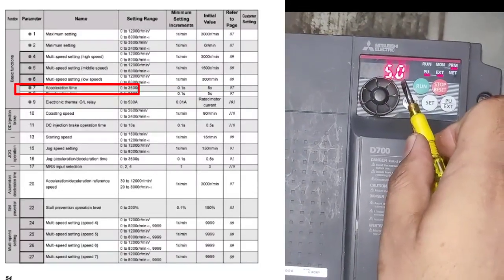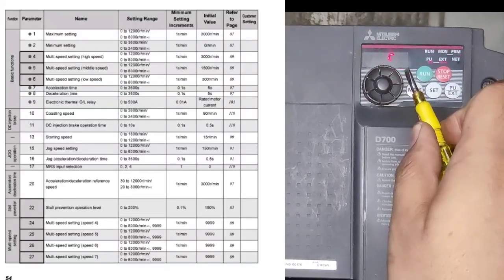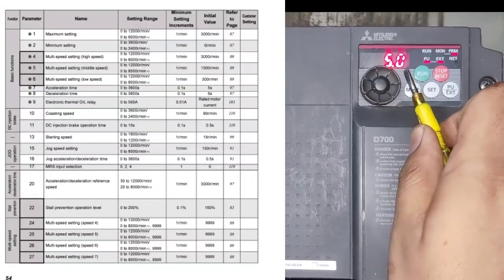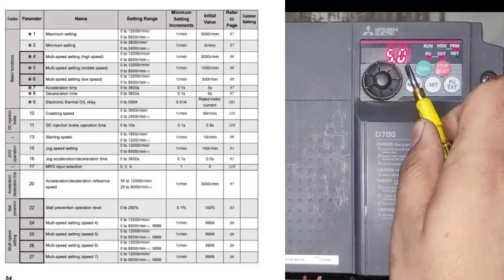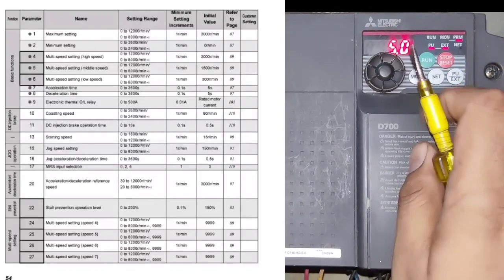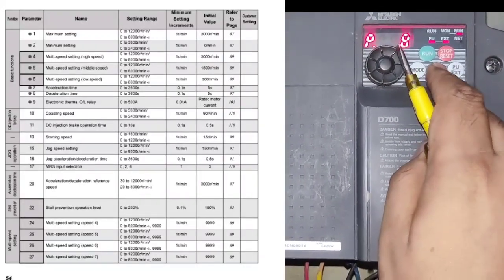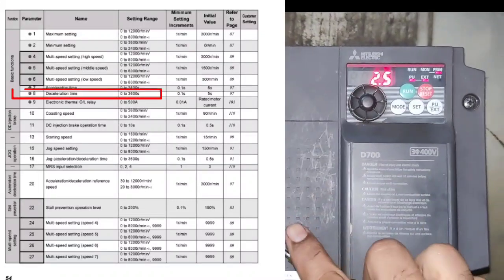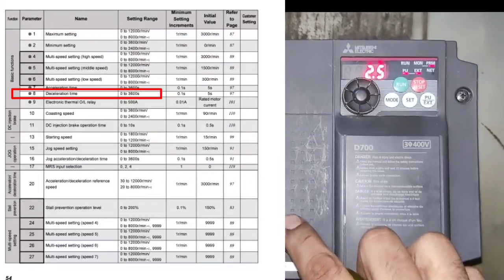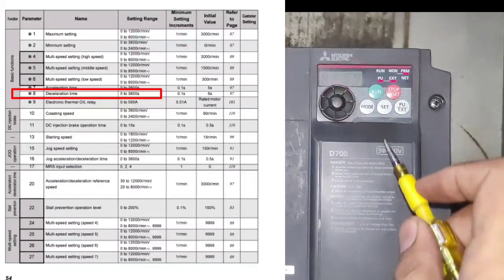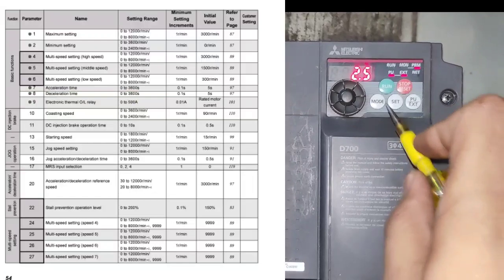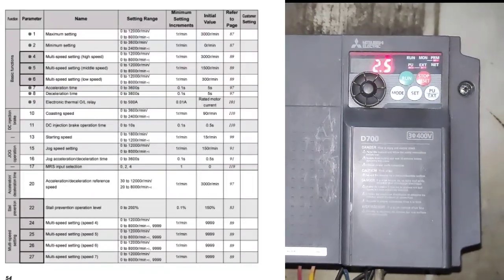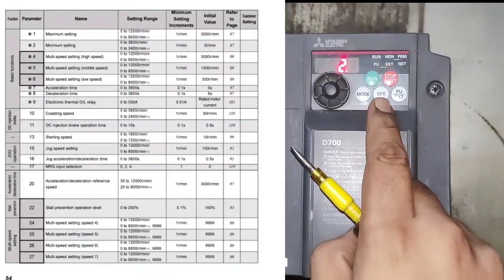P7 is for acceleration time. We set 5 seconds. When your motor starts, the time it takes to go from zero to high speed is the acceleration or ramp-up time — set to 5 seconds. P8 is for deceleration time — we set 2.5 seconds. When we stop the drive, the time to go from high speed to zero frequency is set to 2.5 seconds.